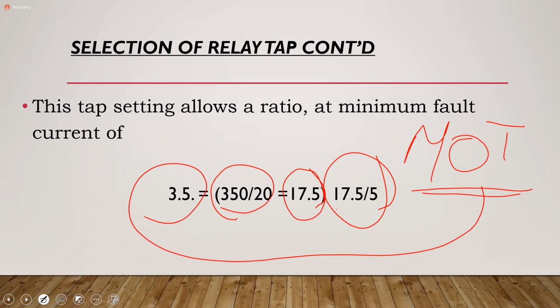So go to your curve now. Everybody have a curve? We're looking at 3.5. If I'm using time dial 0.5, what is the operating time for the minimum fault? 0.2, sir. And if I'm using time dial 1, what is the time for the minimum fault?